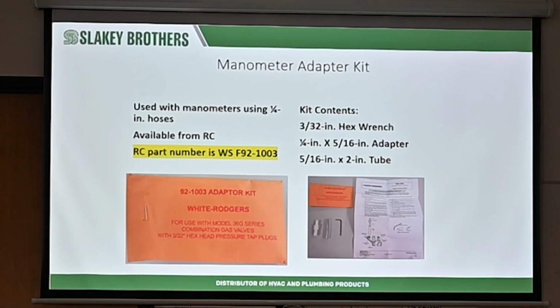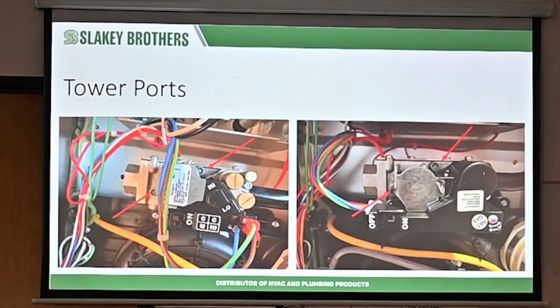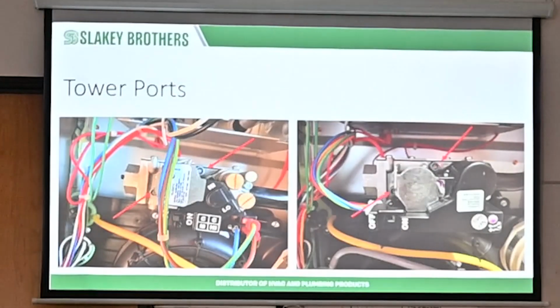Either way, the reason you want this to check your gas pressure is because of our gas valves that we're using nowadays. These tower ports. So this is a 2-stage, and this is the modulating furnace. These tower ports are right there.